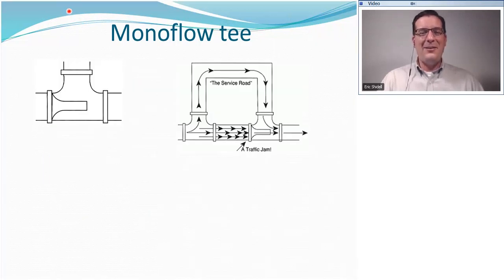This is what they look like on the inside. There's a restrictor in there of one of several types. And here's one example. There's a restrictor. So as water is coming down the main, it's going to jam into that restrictor, and some of it is going to be forced to go around the service road or the bypass or the long way around. And that's how the monoflow system works.